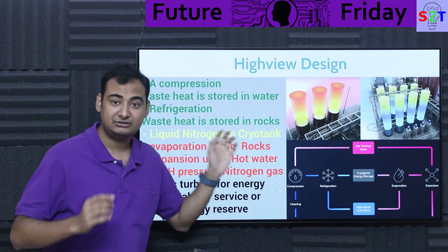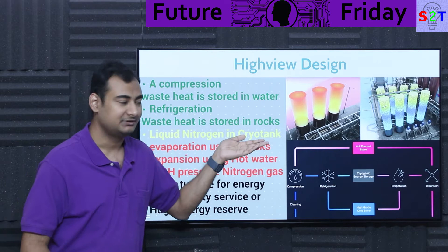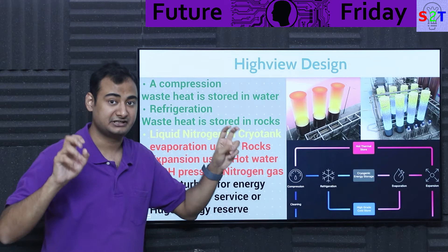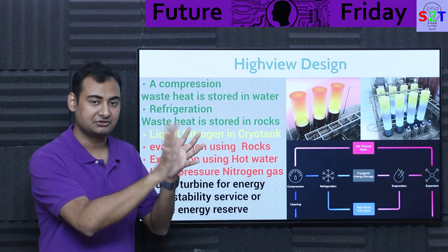After you have compressed clean air, you have to liquefy it. Liquefying also generates waste heat, but it will be relatively low-temperature heat — around minus 100 degrees Celsius. So you have an independent system they call 'high grade cold storage.' The refrigeration unit takes compressed clean air, liquefies it into primarily liquid nitrogen, and has a heat output. That cold output is stored in what turns out to be a rock-based thermal storage system — rocks are very good at low temperatures, unlike water which would freeze and break pipes.